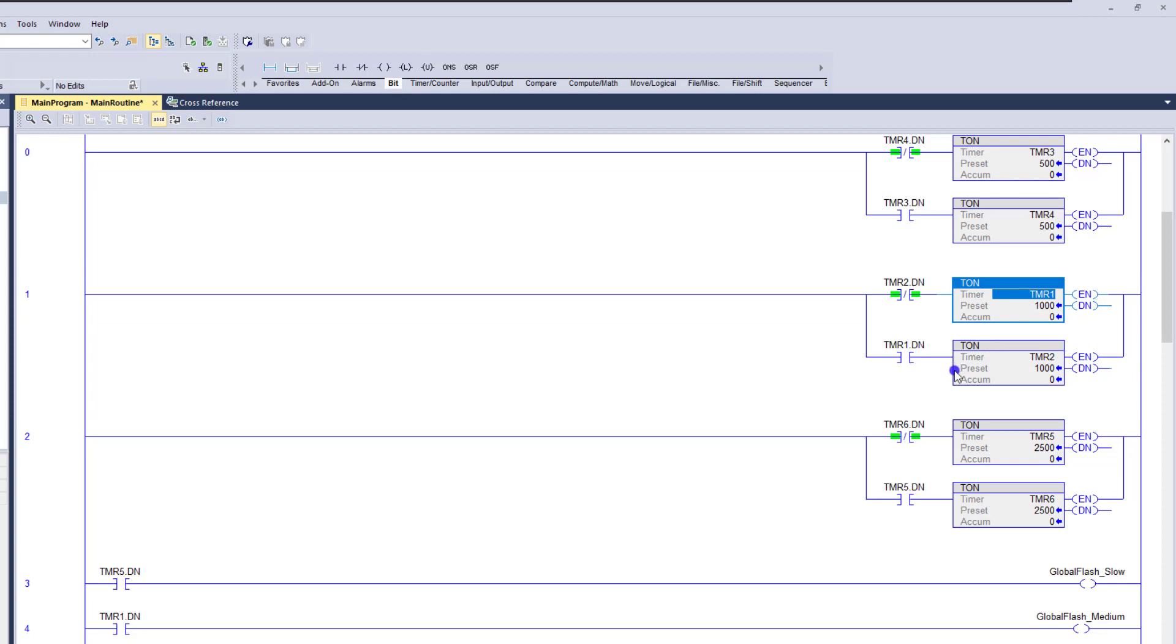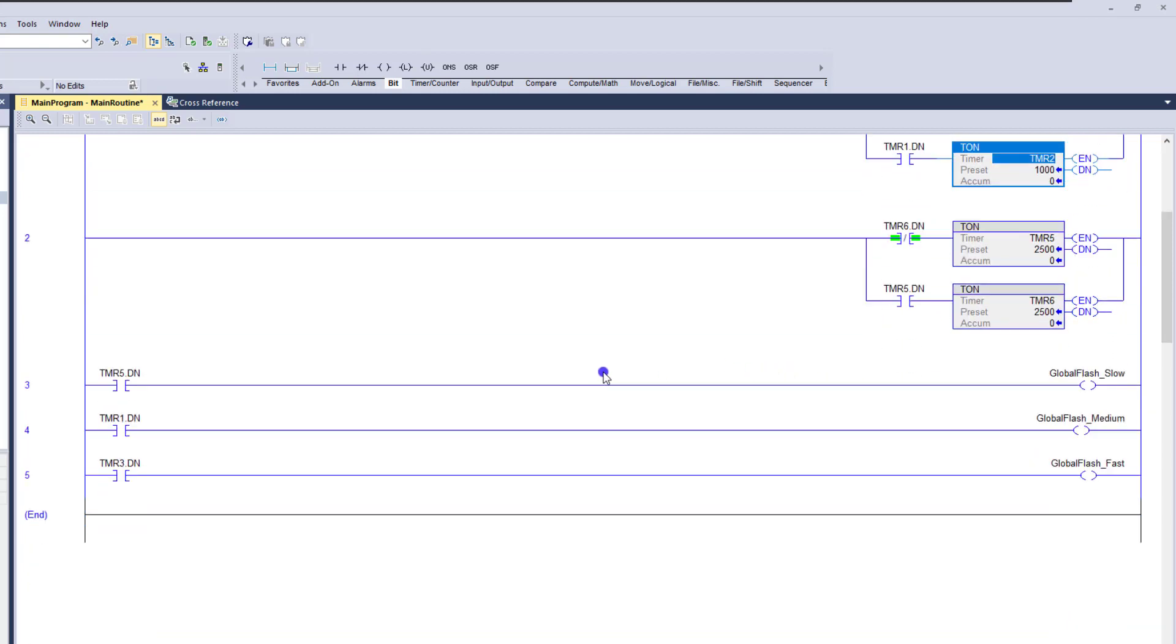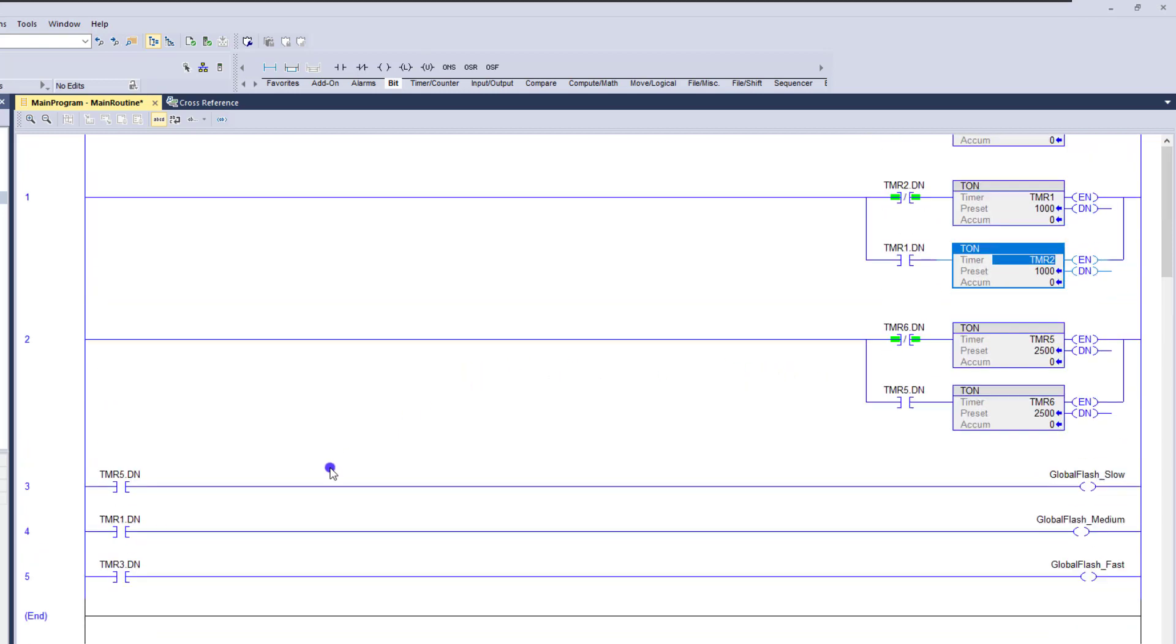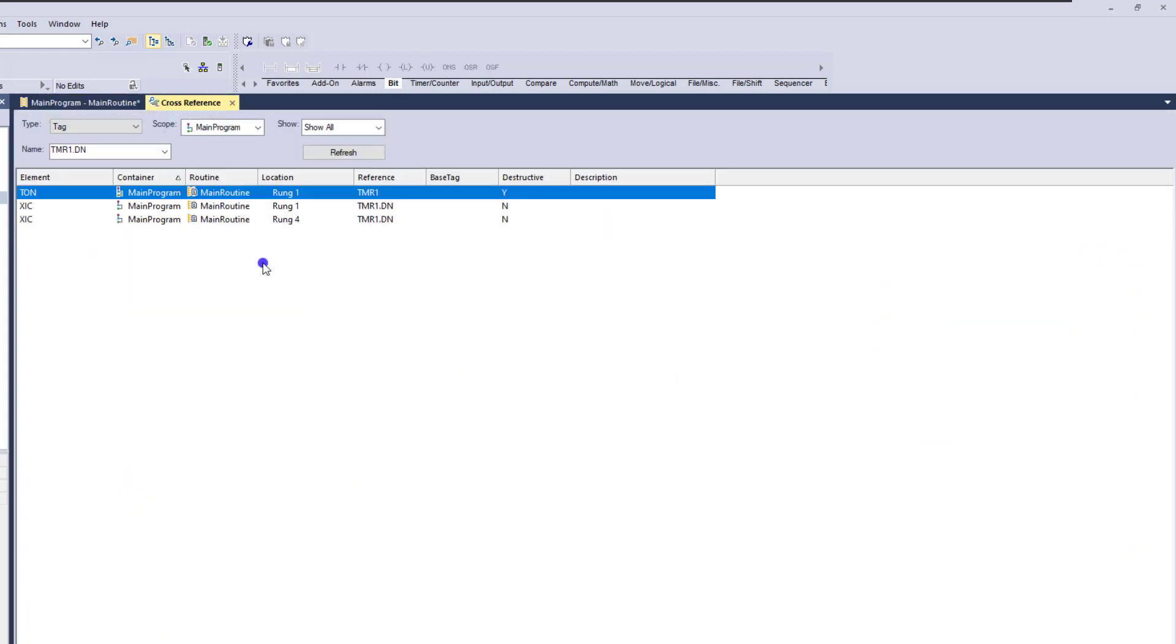So this actually needs to be right here and let's drag that up there and let's change this right here. So now that program is actually right because if timer two is not on, I want timer one on and then when timer one comes on, I want to be able to turn on or have the timer two timing. So just keep that in mind. It's easy to find something and troubleshoot something. So now if I search that bit, the very same bit, it's going to be different. There's only three of them.